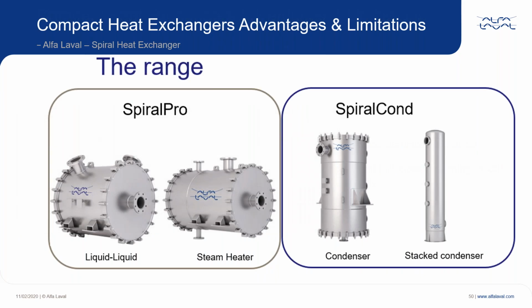So, moving on to the next one, our spiral heat exchanger. It's split into two ranges, the Spiral Pro and the SpiralCond. The Spiral Pro contains our liquid unit and our steam heater spiral. The SpiralCond is basically various different condensers. The stack condenser can contain several spirals in one assembly, so you can have multiple passes.